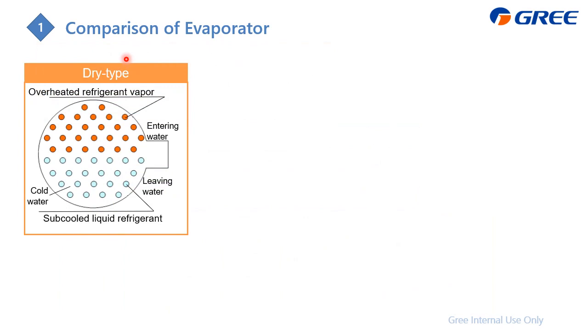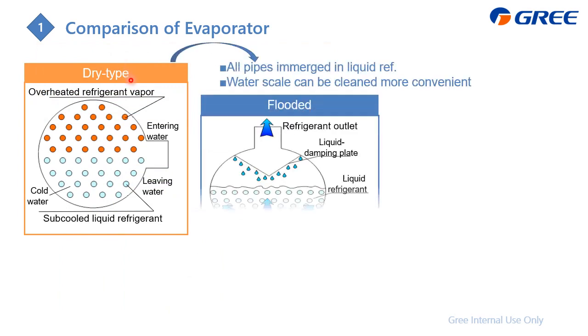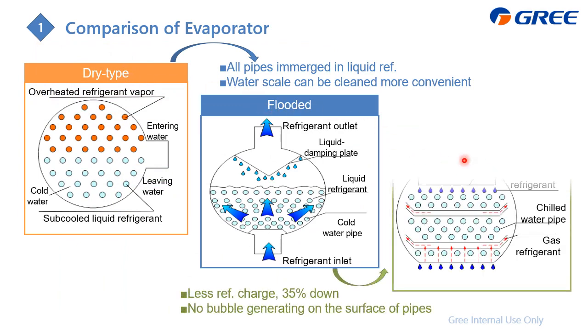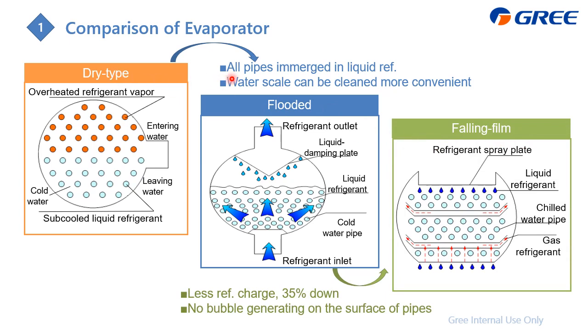And this is the sectional view of the comparison between the dry type, flooded type, and falling film type. For the first generation, the dry type, the efficiency is not that high, so we upgraded to the flooded type. The feature is that all pipes are immersed in the liquid refrigerant, and water scale can be cleaned more conveniently because the water scale is on the water side, just inside the tube. That's why you can use either mechanical or chemical methods to clean the water scale, and it is also very easy.